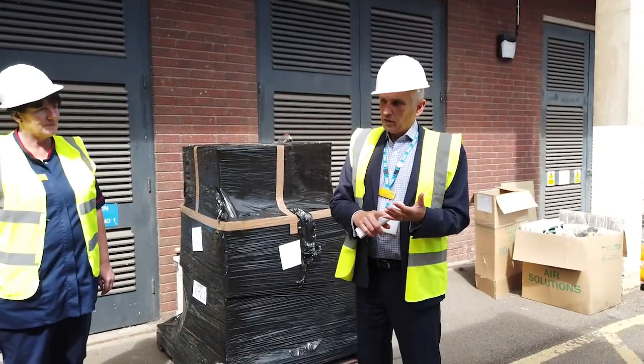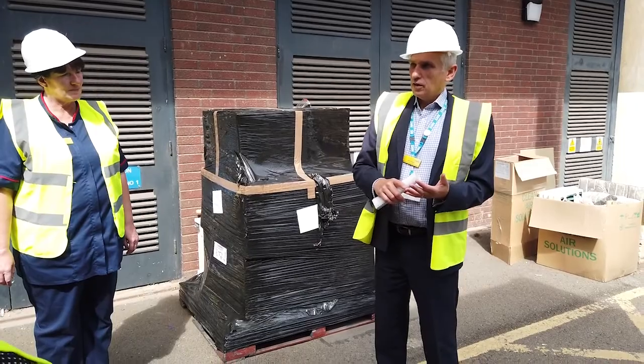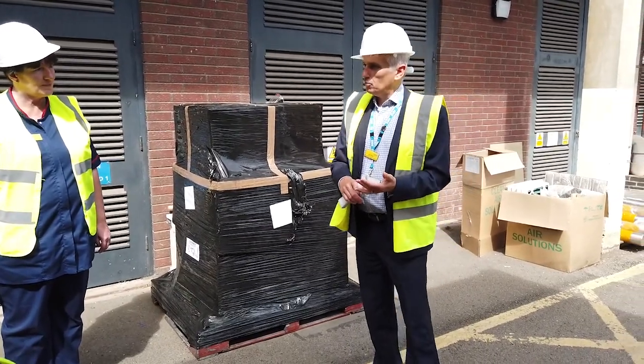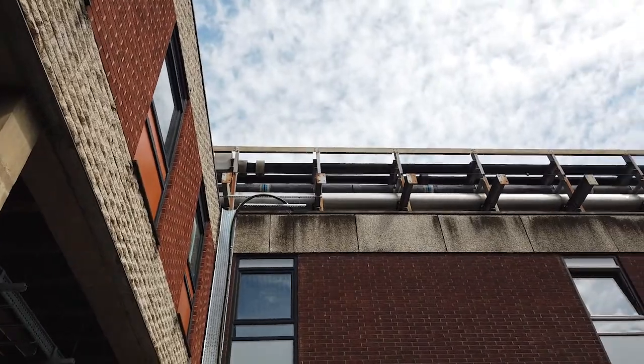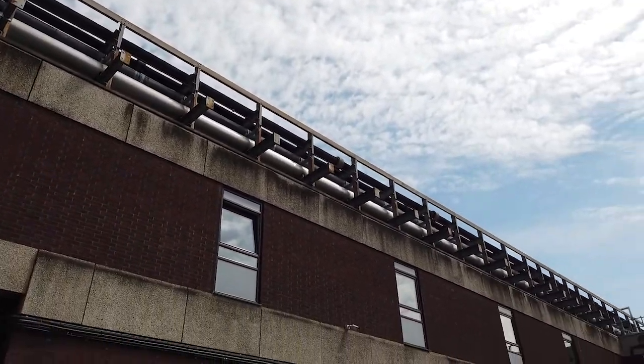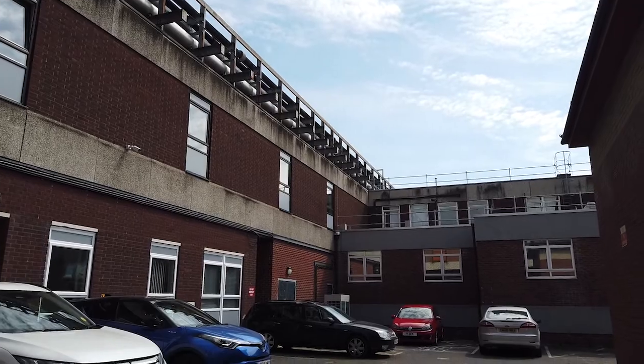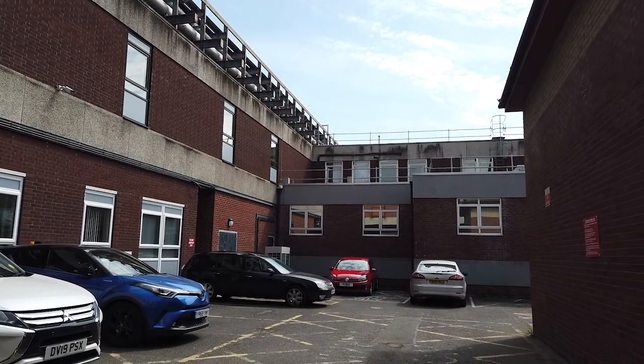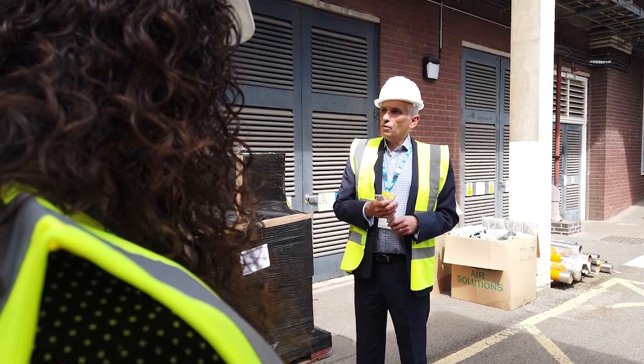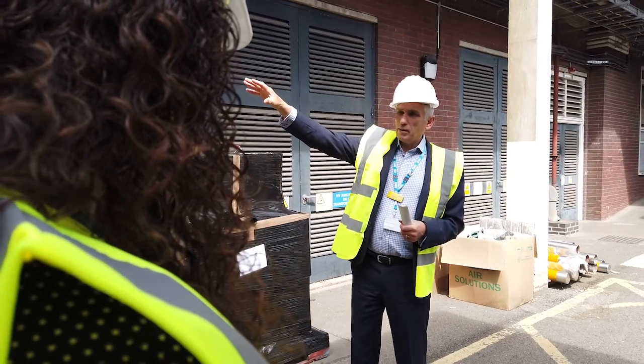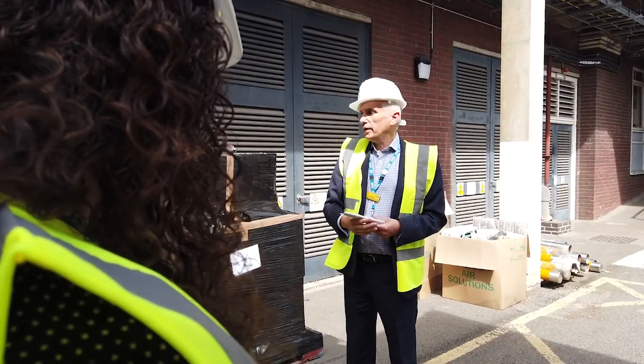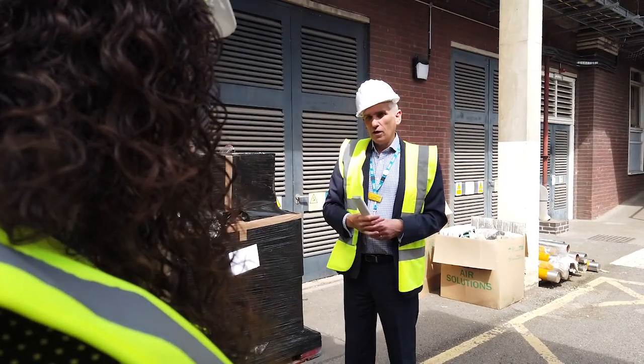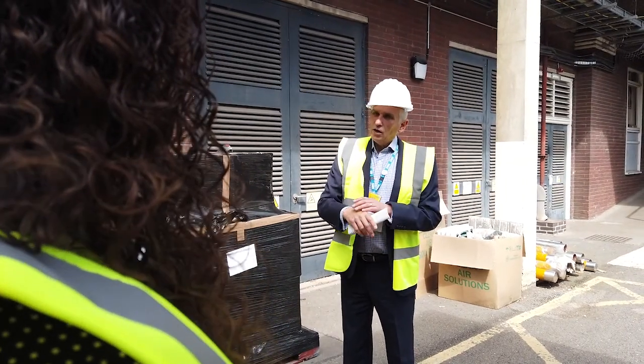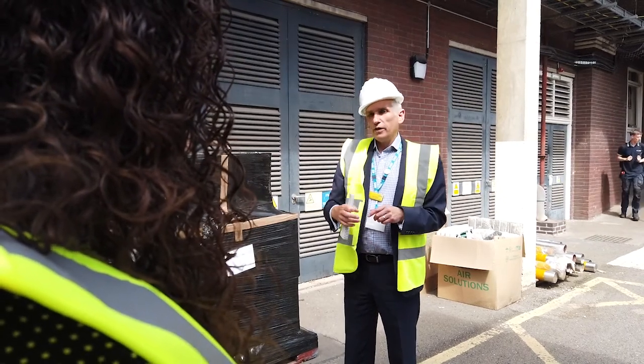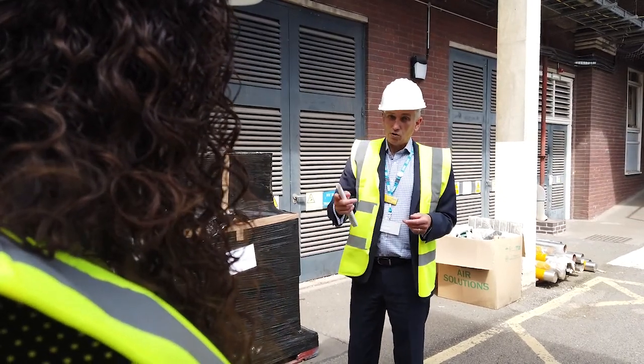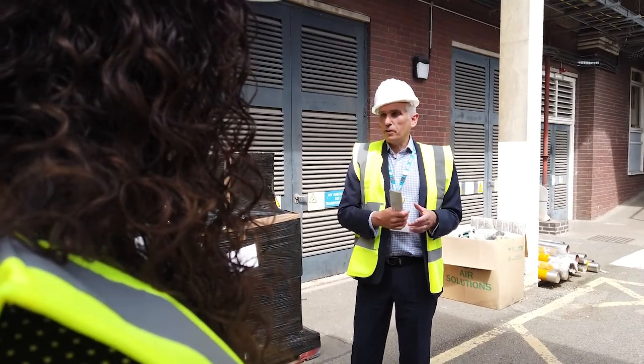We're generating heat and we're generating electricity. And what are we doing with that energy? We're transporting it from one place to another via pipes or via wires. And why do we transport energy from A to B? We do that so that energy can do work and process for us. So, for instance, at the far end of the site there will be a plant room with an air handling plant that serves the operating theatres. We take that heat in the pipes and run it through heating coils, or cooling coils, to heat or cool the air going into an operating theatre.